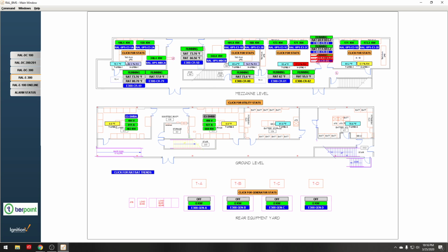So our temperatures to the UPS rooms are mounted right here. So we're looking at changing how we're operating these CRACs soon, so we don't have 55-degree temperatures in our UPS rooms. UPSs just don't like running that cold. It's not good for the batteries or anything of that nature.